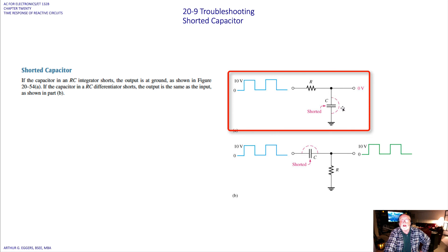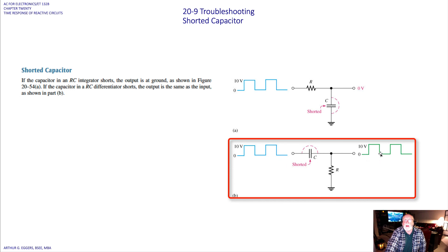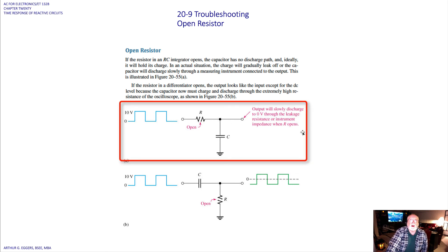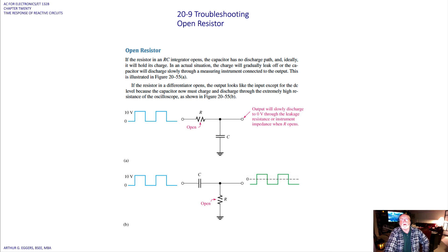With a shorted capacitor — where there's a dead short through it, possibly from too much current or bad material — you end up with either nothing or a straight pass-through on your signal. If you've got a burned-out or open resistor, the output will slowly discharge to zero through leakage in the resistor or instrument impedance. In a parallel configuration, you again get a pass-through. In the lab, check whether your equipment has the capability to test and simulate these types of output faults.